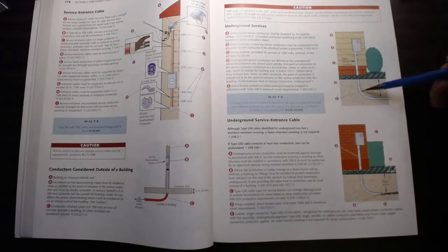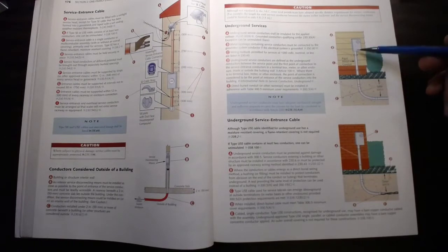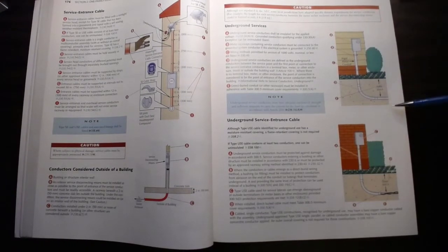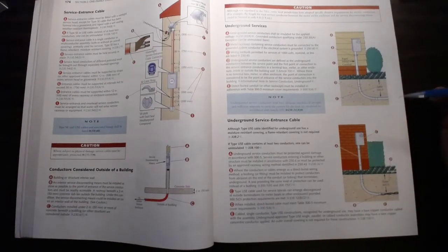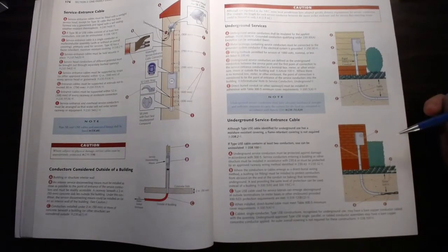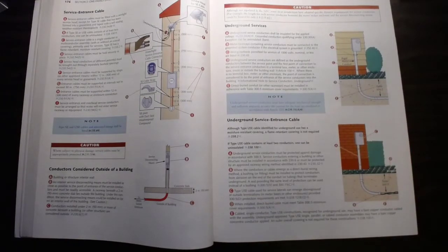There may be a minimum 3-inch size in the ESR requirements for that utility that have to be abided by. And so you can't just run any conduit out there. You need to work with the utility to find out what the size is. And of course, we know that for a 200 amp panel, when we size the conduit, it's not going to be 3-inch. But 3-inch gives the opportunity to go with the largest conductor. And frankly, the utility will make it easier for them to pull it, and they would like a larger conduit. So we have to accommodate for that.